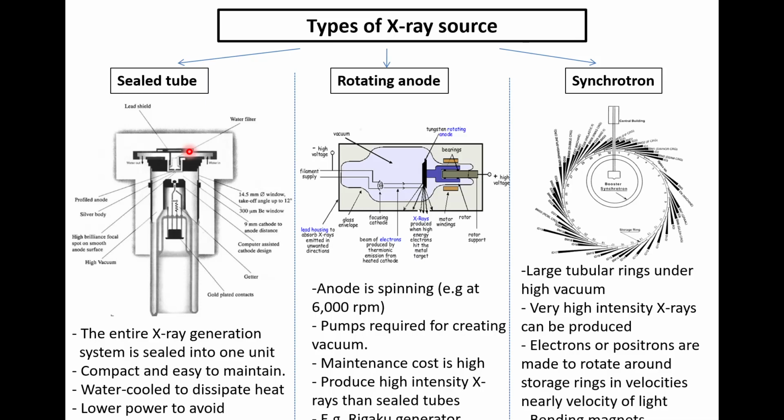from these sealed tubes. To combat that, sometimes people put certain water channels in this sealed tube which can actually lower the temperature of the anode. The water will come and go near where the anode is present, not directly interacting with the anode, but there is a cold water chamber beside the anode, which will keep this anode colder, but still this anode's half life will be very less.